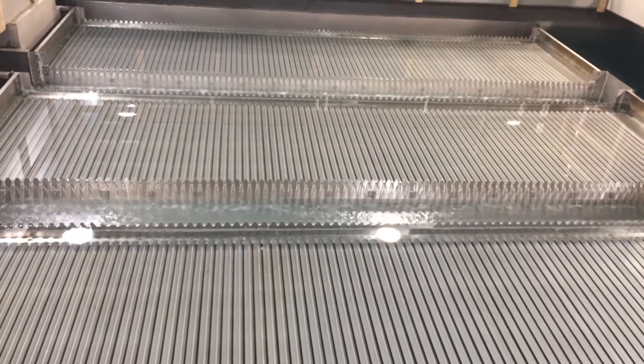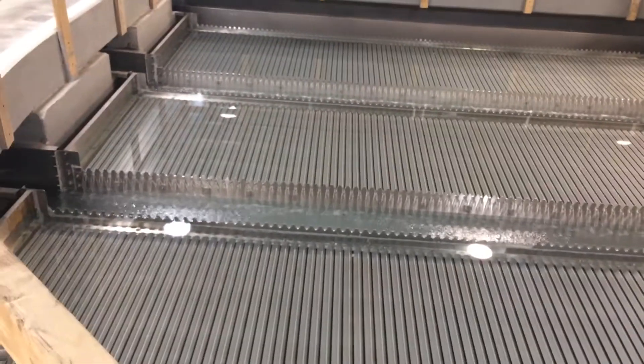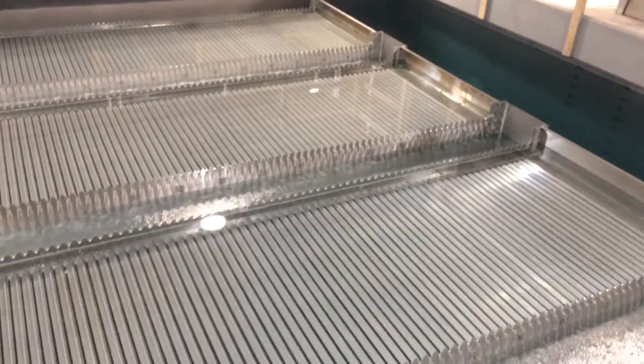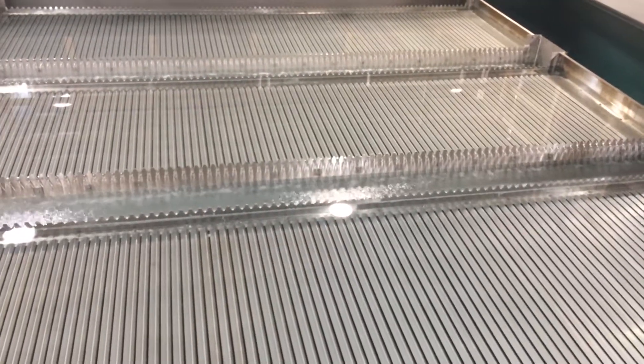We have our mega settlers, our plate settler system in the sedimentation basin. Here you can see the plate settlers. The plant operator just took a manual sample, which he takes once an hour. The manual sample was 0.3 NTU.